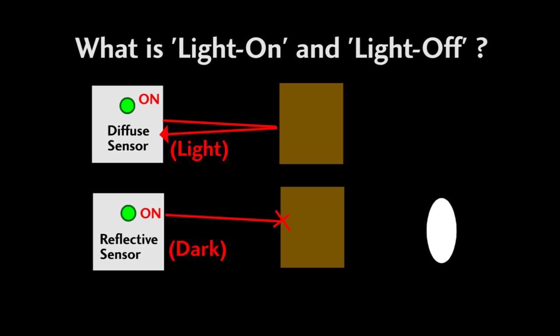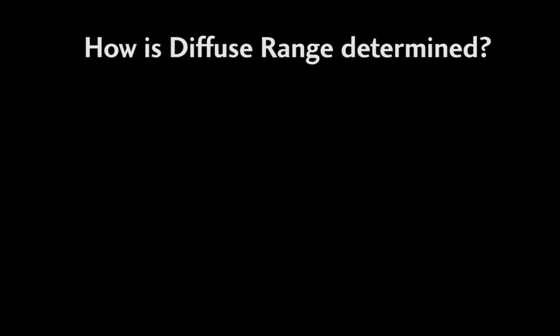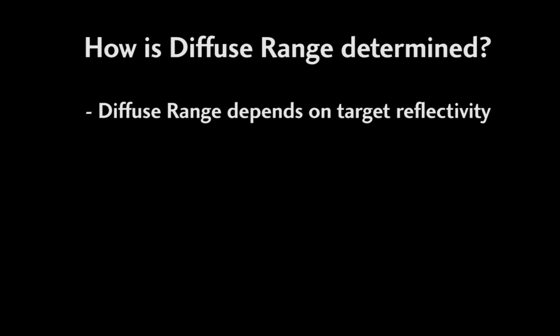Some sensors can be configured to either light-on or dark-on mode of operation. Diffuse sensor range is dependent on the reflectivity of the target. In some cases, a dark object may reflect light better than a light colored object. Diffuse sensors are specified by the distance at which they detect white card stock.